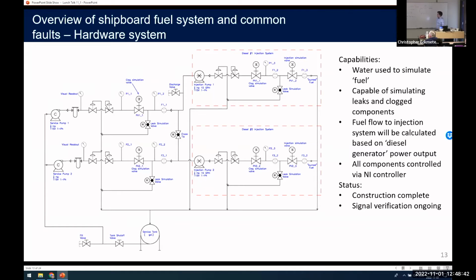And then this is the overview of the fuel system. The fuel system is set up similarly to the cooling system. It has 2 parallel paths to implement redundancy and emulates the injection of 2 high pressure fuel systems. We have a low pressure supply system you can see on the left. This is mimicking the pumping of the fuel from tanks up to the high pressure fuel rail or up to the diesel engine system, and then the high pressure simulates the on-engine fuel dynamic systems that you can see boxed in red, 2 parallel paths. And Ethan is the undergrad student currently working on implementing the dynamics of fuel injection.